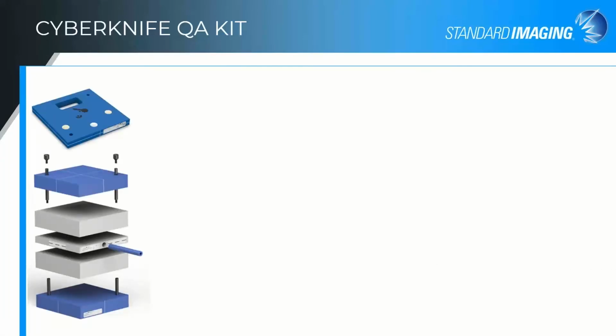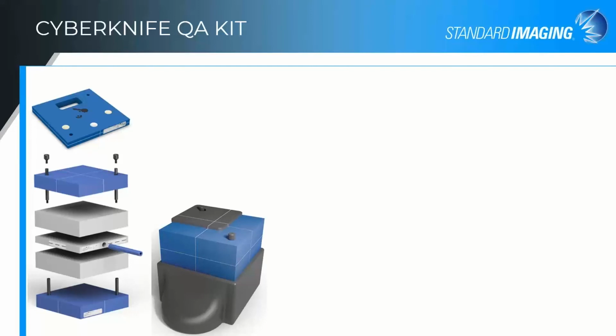No presentation about CyberKnife is complete without talking about our full package solution. Our stereotactic dose verification phantom, SDVP for short, is a wonderful and commonly used tool. This compact phantom is versatile and easy, like I said, for QA commonly done with detectors and film. The top hat and cradle are newer additions to the SDVP. The cradle lifts the phantom to position it for posterior lesion QA. The top hat includes tighter fiducial marker placement to facilitate fiducial tracking for smaller targets.